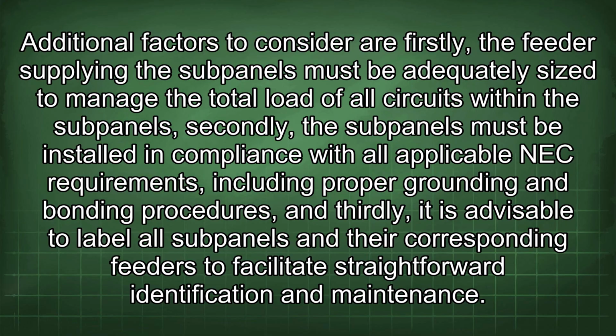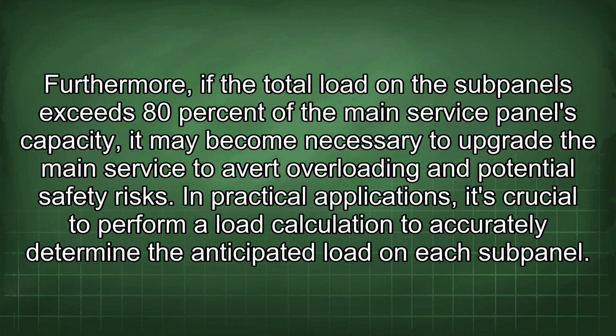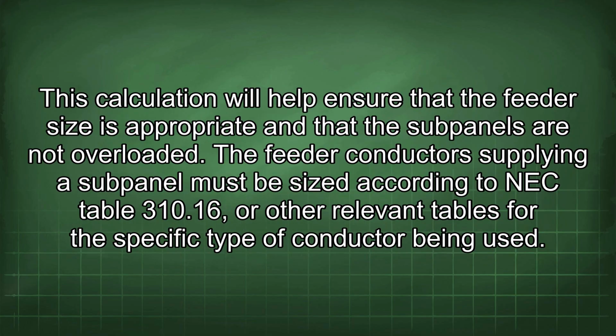Secondly, the subpanels must be installed in compliance with all applicable NEC requirements, including proper grounding and bonding procedures. And thirdly, it is advisable to label all subpanels and their corresponding feeders to facilitate straightforward identification and maintenance. Furthermore, if the total load on the subpanels exceeds 80% of the main service panel's capacity, it may become necessary to upgrade the main service to avert overloading and potential safety risks. In practical applications, it's crucial to perform a load calculation to accurately determine the anticipated load on each subpanel. This calculation will help ensure that the feeder size is appropriate and that the subpanels are not overloaded.